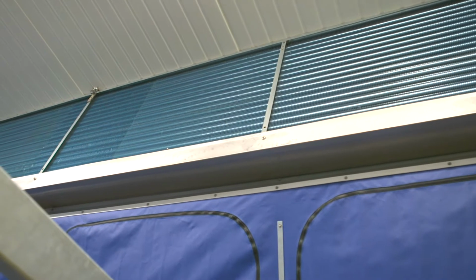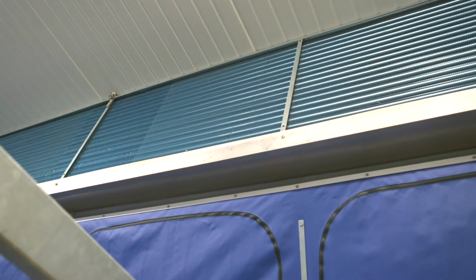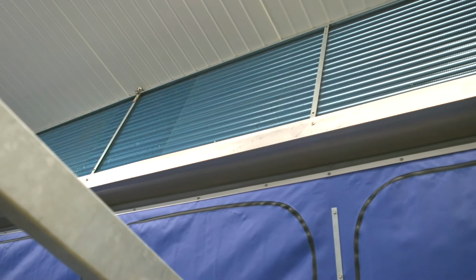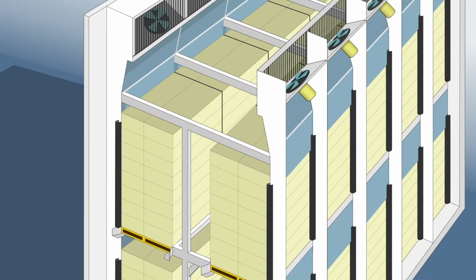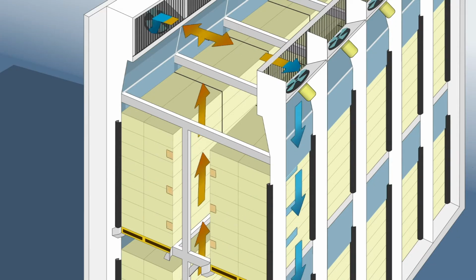Room temperature is controlled by these large horizontal evaporator coils and heating elements that run along the top of the rooms above the fans. The fans draw the return air that's already passed through the pallets back up and through these coils. The evaporator coils warm or cool the air as needed before sending it back through the pallets.